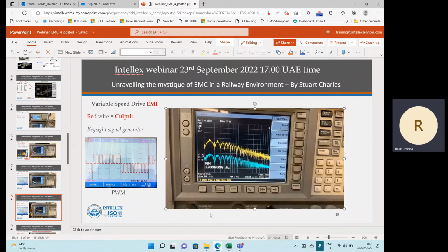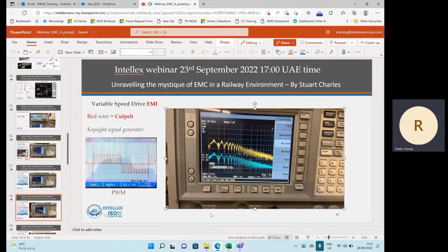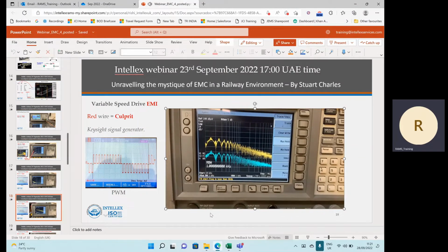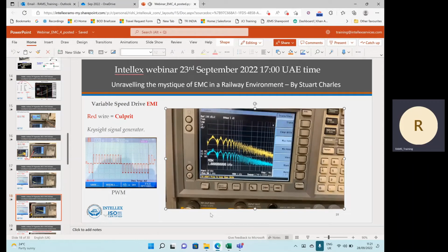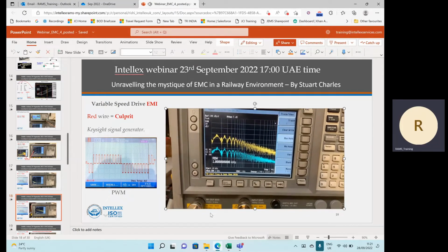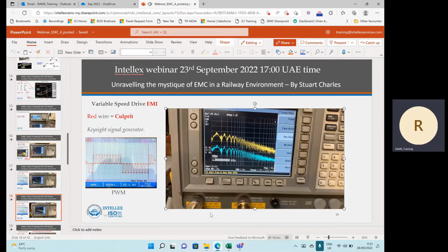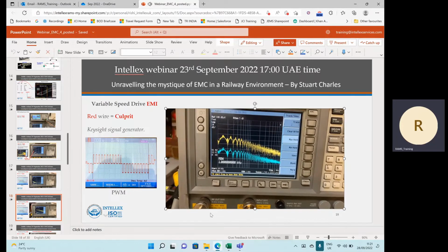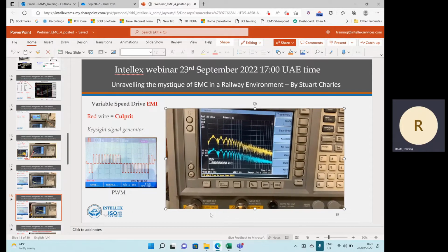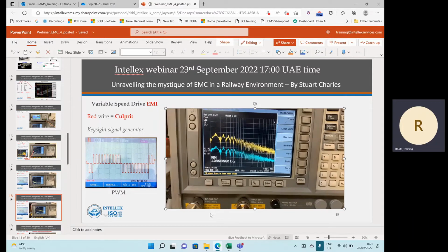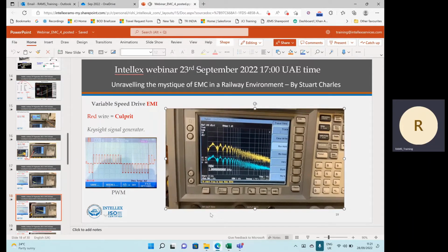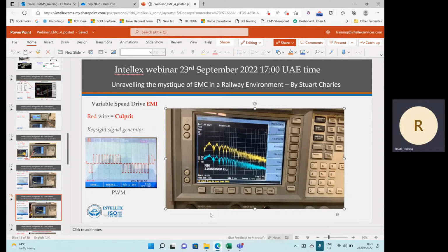We're about 2, 2.5, 2.25 boxes down, 20 dBs. Our external current that should flow back through the VSD SWA or local earth, a tenth of it, 20 dBs, is 10 times, a tenth of it is still flowing through our external earth.